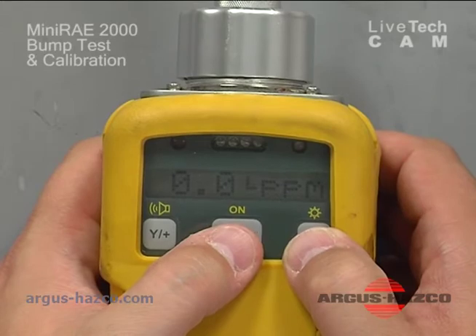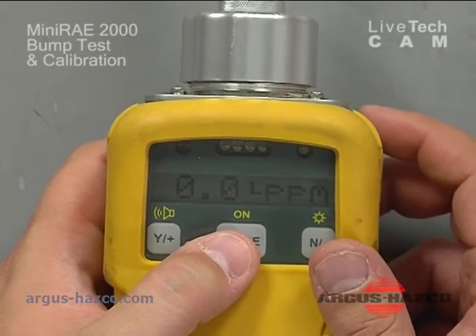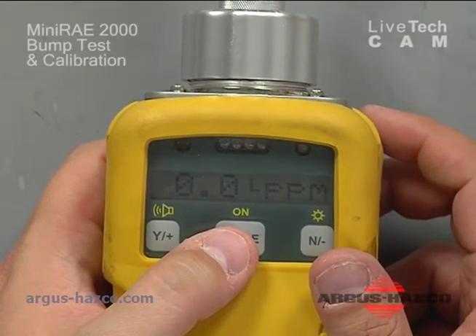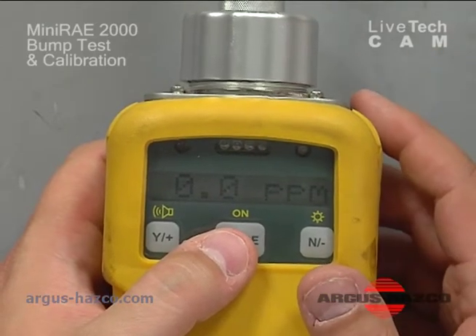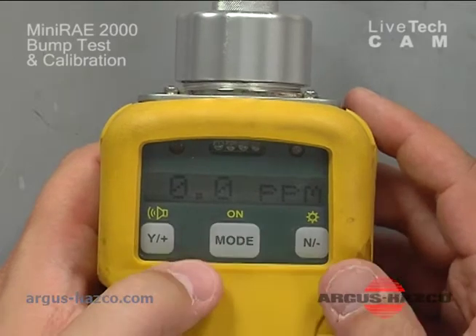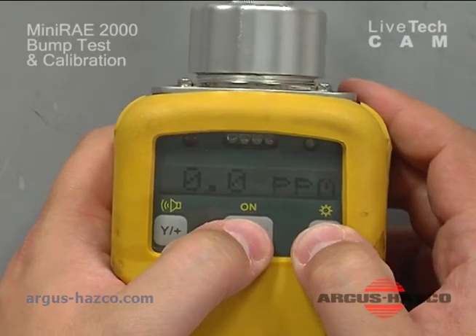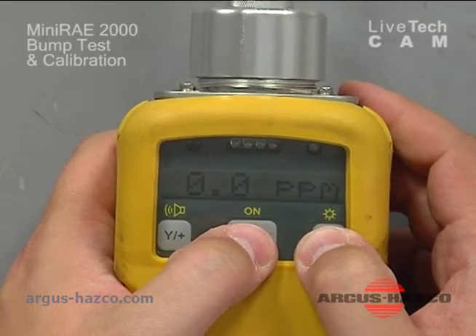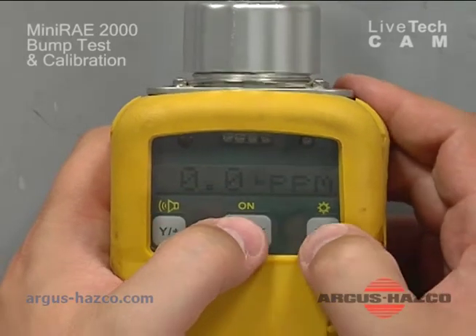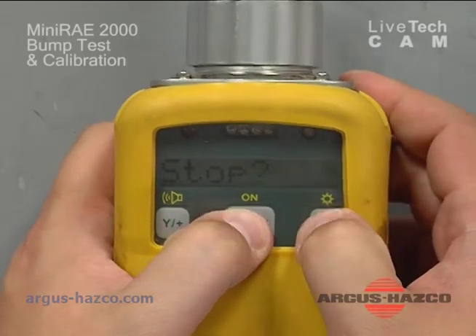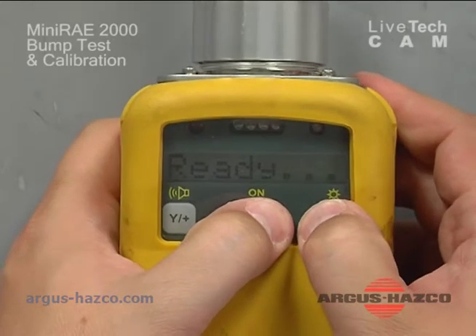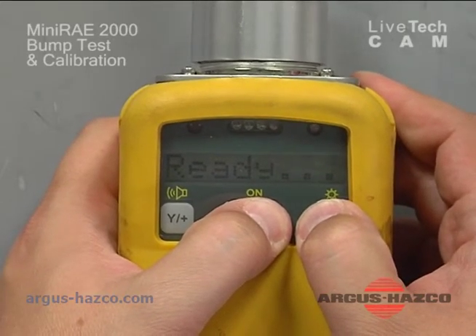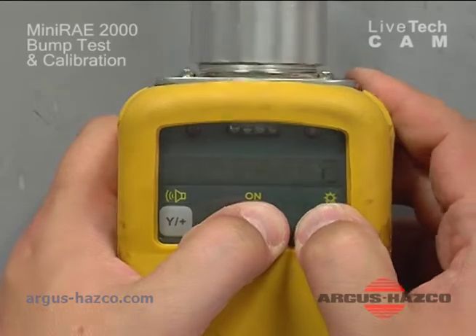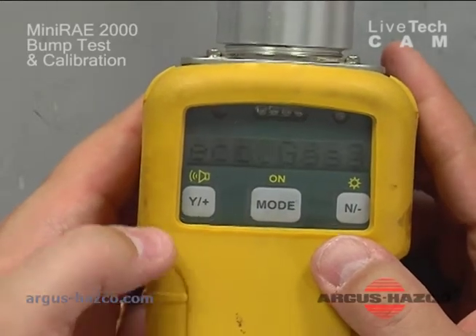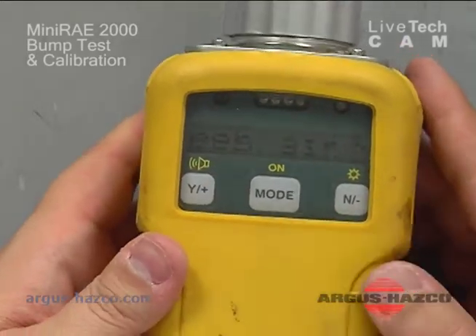And during the bump test, if you apply the gas and went to 100 ppm plus or minus about 10%, some people go as low as 2 to 5%, as high as 20% for a tolerance. That's really on your individual company's needs. But at this point, since we were over at 9,999, we know it definitely needs to be calibrated. So we're going to press and hold the mode and no button until it says calibrate. Select gas, you put yes, you want to calibrate.